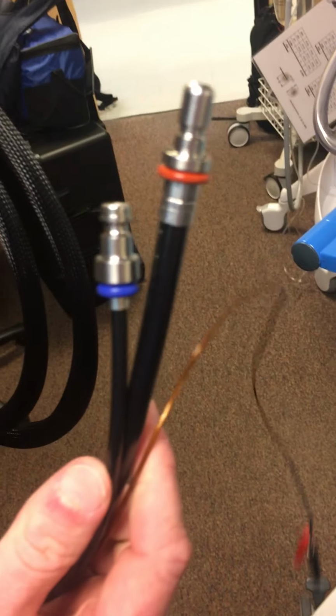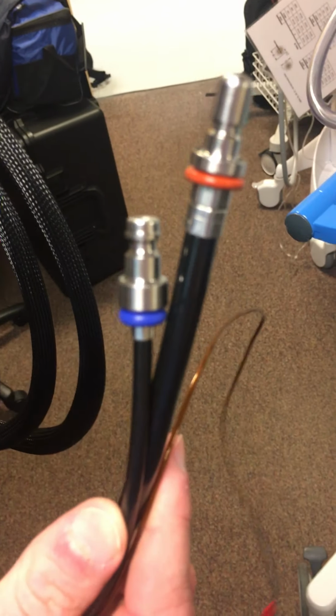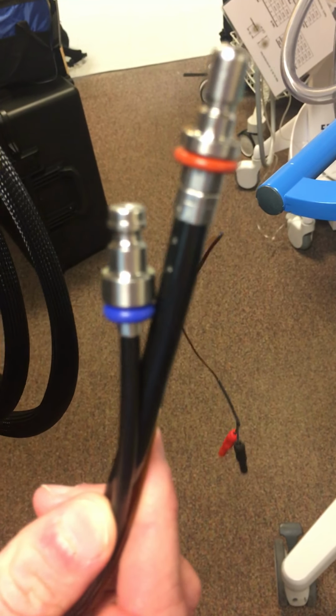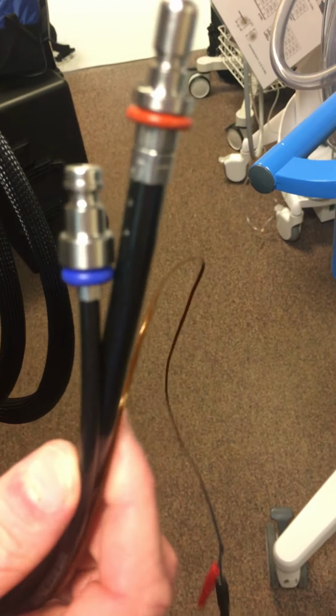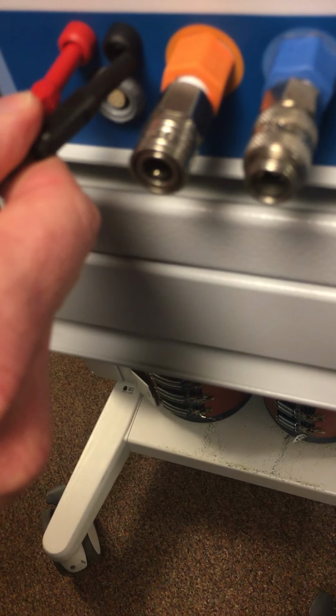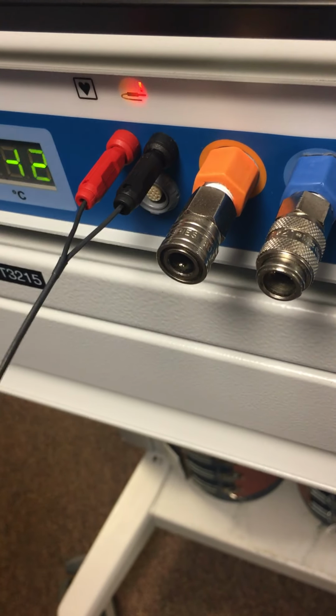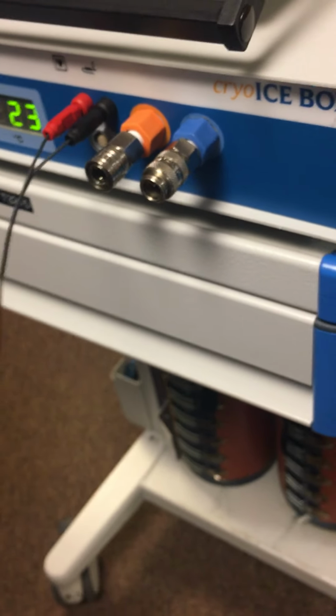This right here is the connection that will be passed off to the circulator or vendor once we get it cracked open onto the field. Again, all of the connections are color coordinated: red and black, orange and blue. So we'll go ahead and connect at this point. Temperature gauges go in, red with red, black with black. The other two are quick coupling.